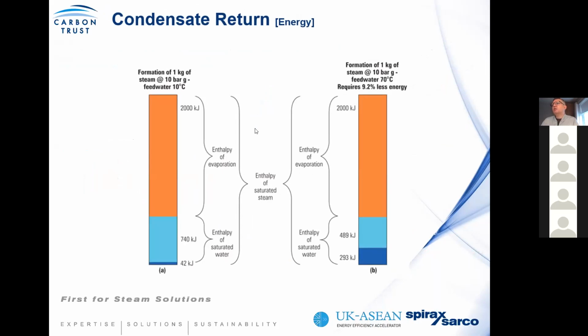So when we start looking at condensate, why you want to get condensate back is, for example, when you look at 10 bar condensate and you look at feed water at 70 degrees, getting condensate back can reduce the energy demand of your boiler quite significantly, because the enthalpy of the water is quite significant in comparison to boiler feed water at 10 degrees. So in this case, where you're adding makeup water, this is your start point. However, when you're returning condensate, for example at 70 degrees, you can see your starting point is higher and you have to add less energy into the system. So in other words, every effort should be made to recover condensate at the highest temperature possible.